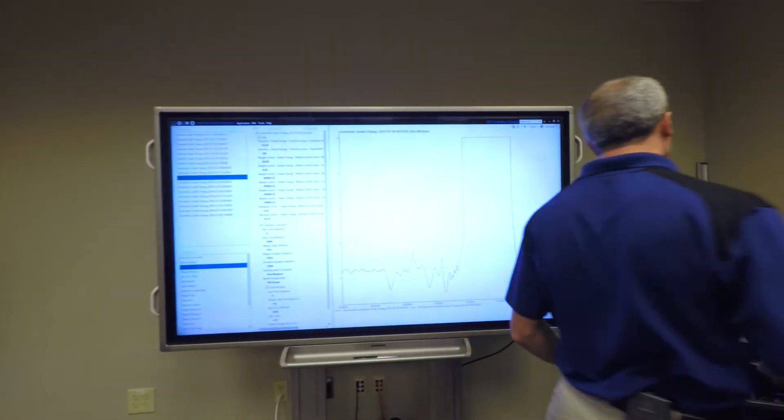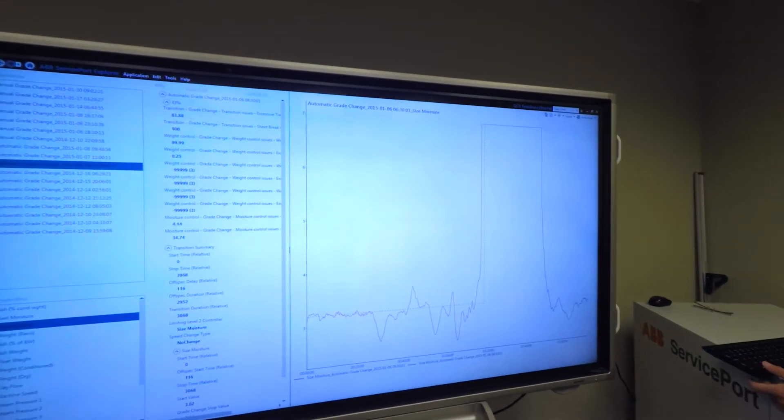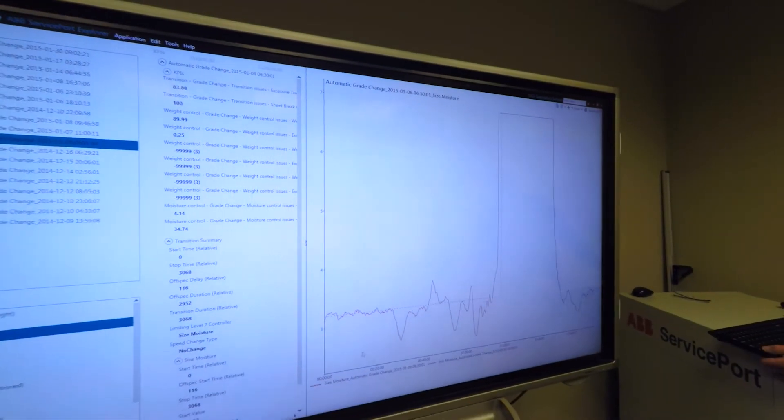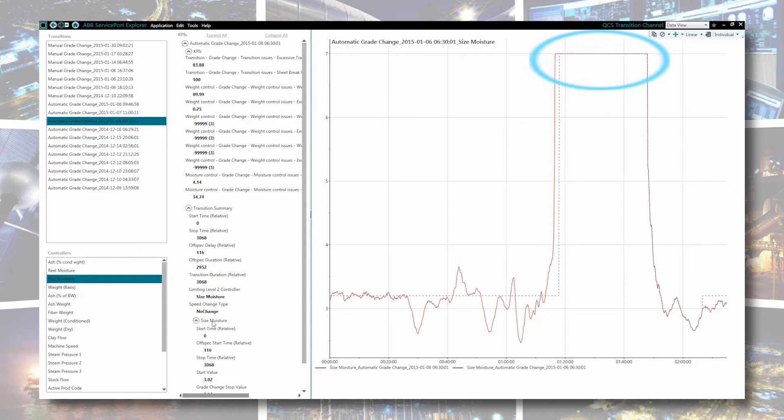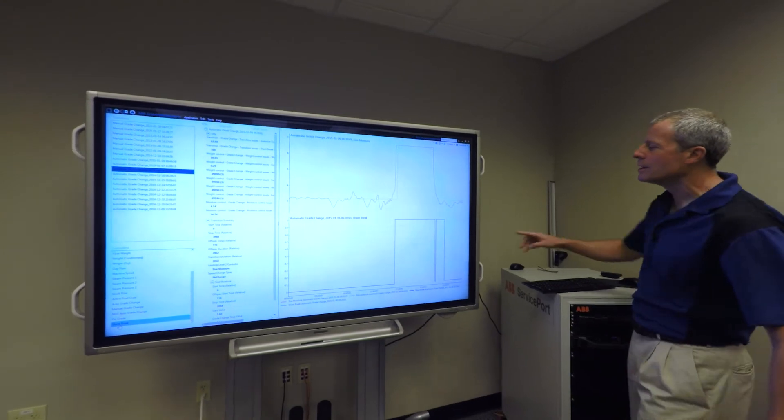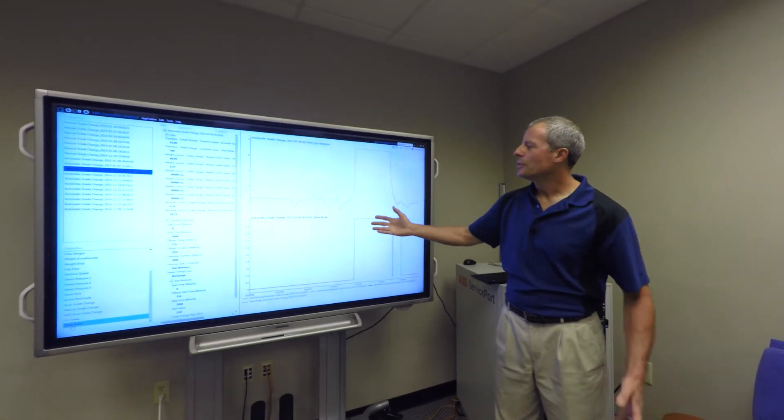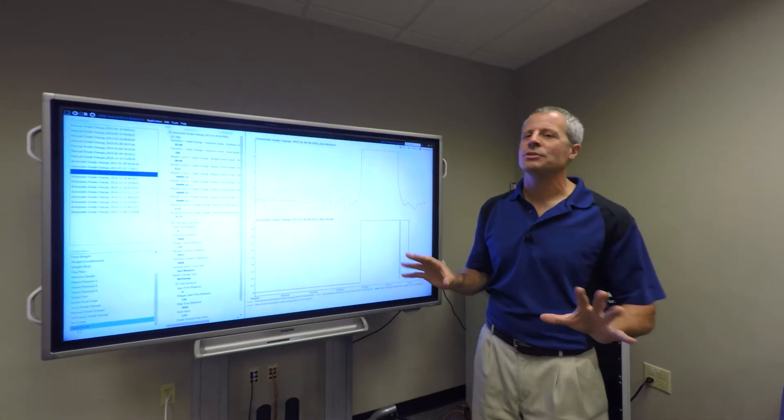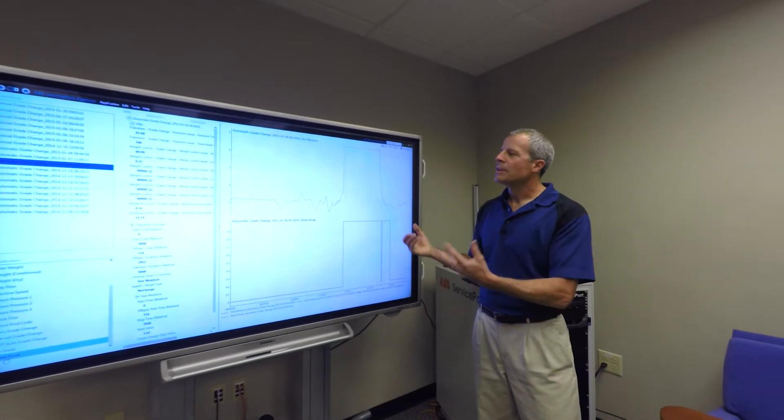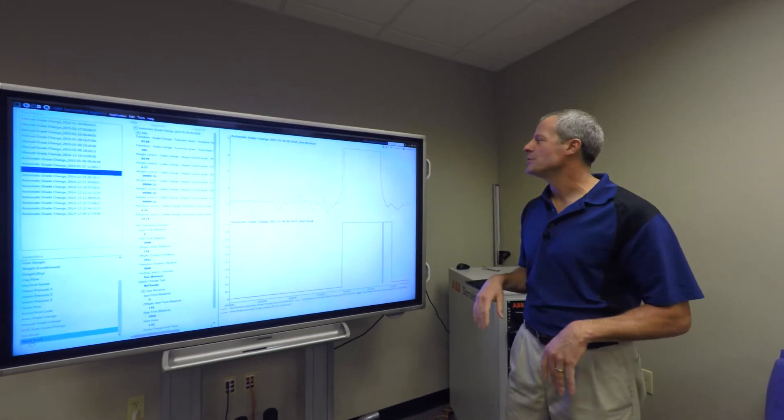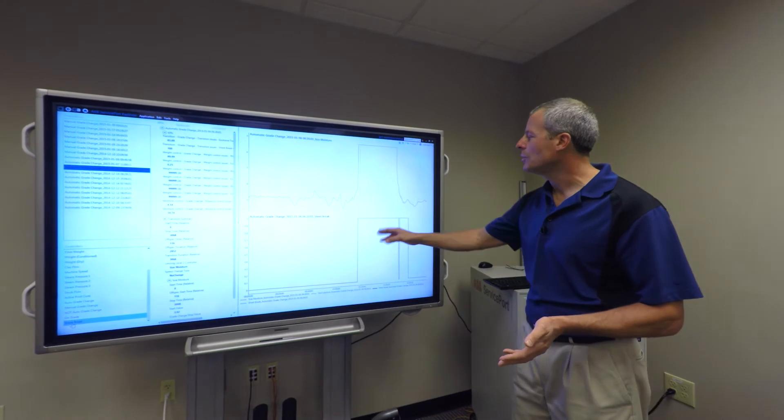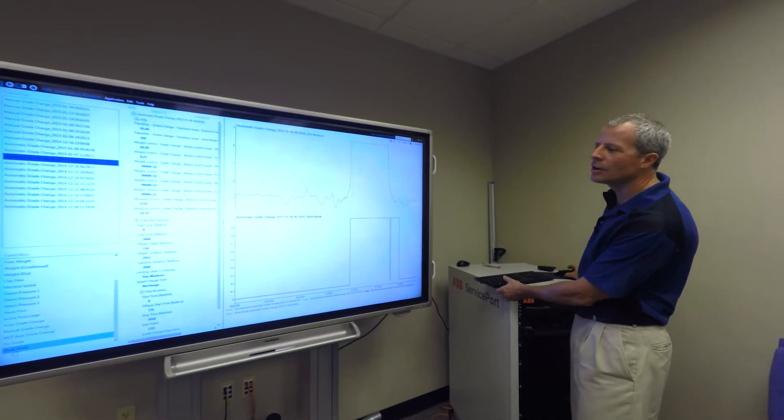In addition to the size moisture, let's take a look at what other areas we want to look at. You notice that the size moisture has a pretty dramatic increase, and then there's a flat area where the measurement looks like it stopped updating. If we look at the size moisture, this is an indication of a sheet break. This is a pretty obvious case. Obviously the transition time is going to be affected by a sheet break. We've quickly drilled into the transition time and found a transition that was not performing as well as possible. This one was related to a sheet break that occurred.